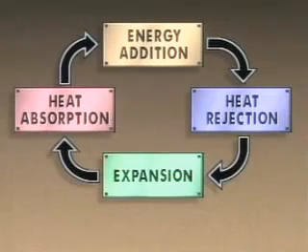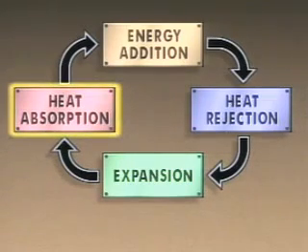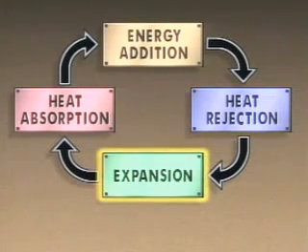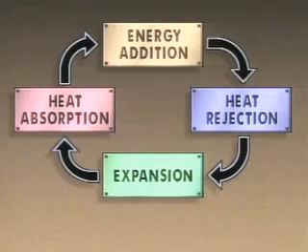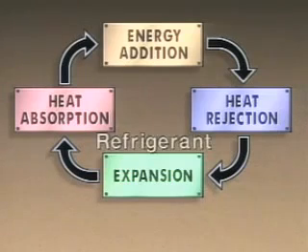We can use an illustration to identify the steps in a refrigeration cycle and see how the cycle works. The cycle we'll look at is called a vapor compression refrigeration cycle. A typical vapor compression refrigeration cycle has four basic steps: heat absorption, energy addition, heat rejection, and expansion. Since the steps repeat, the cycle is a closed system designed to operate continuously. The cycle uses a fluid known as a refrigerant to transport heat through the system.